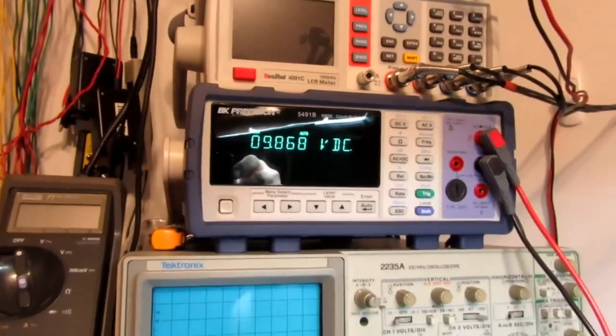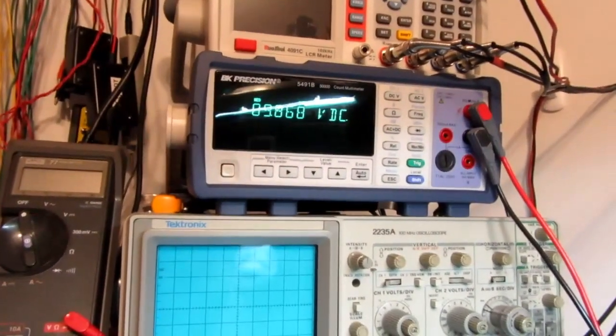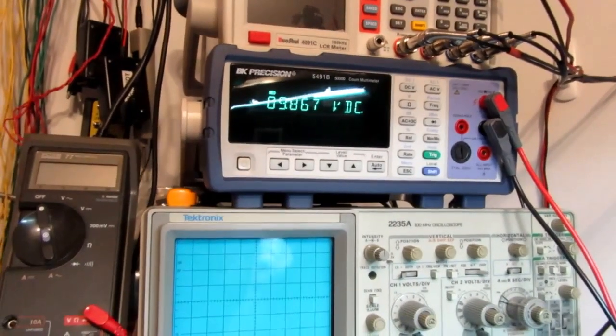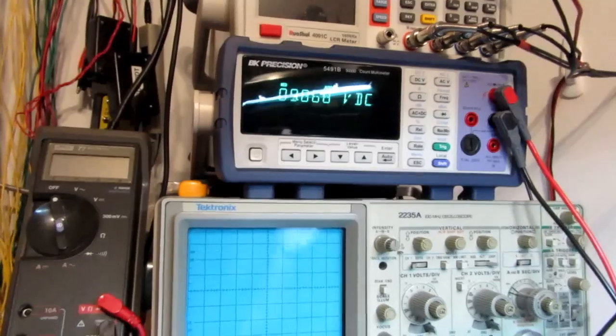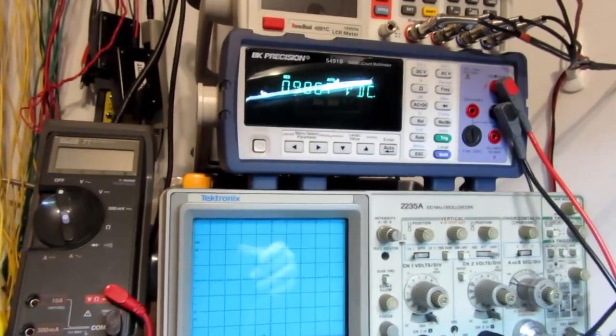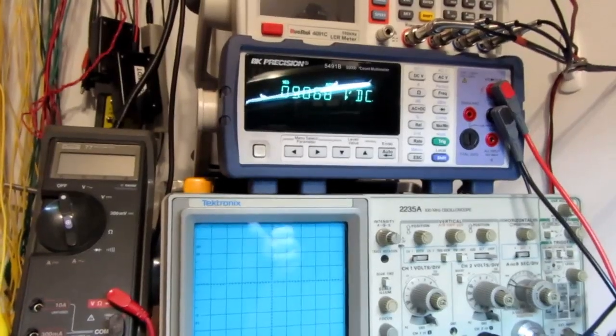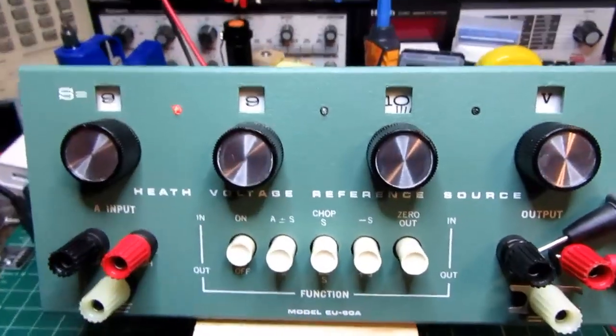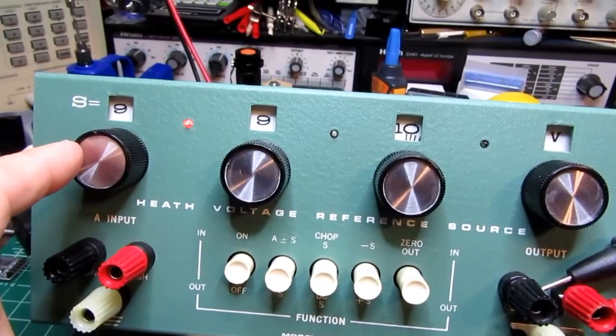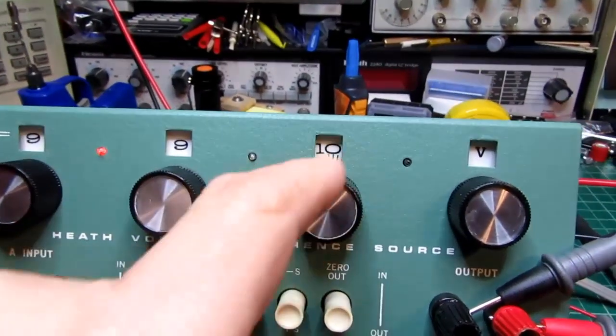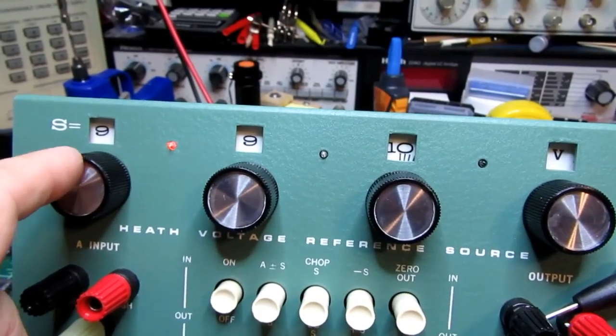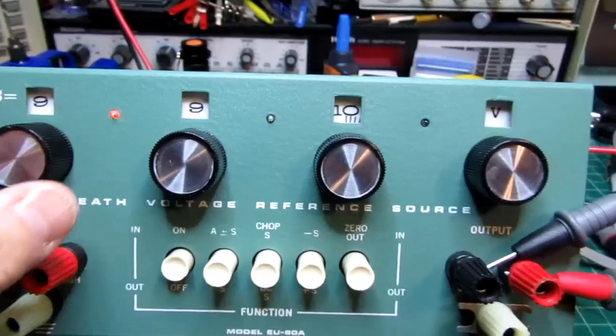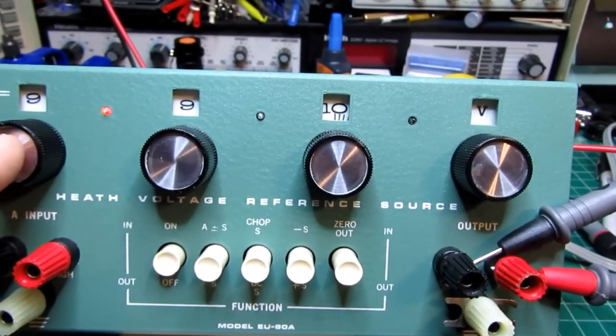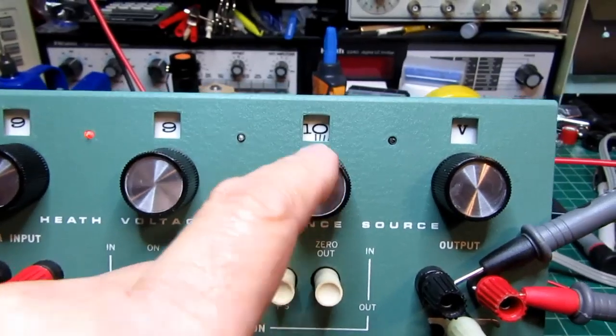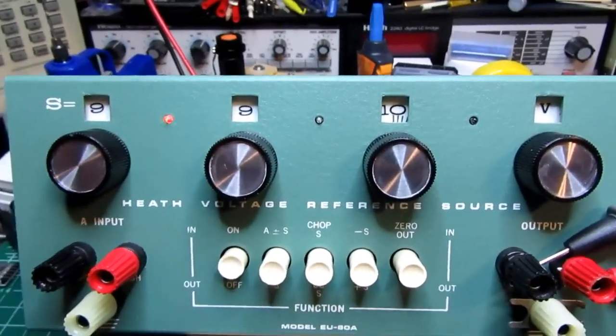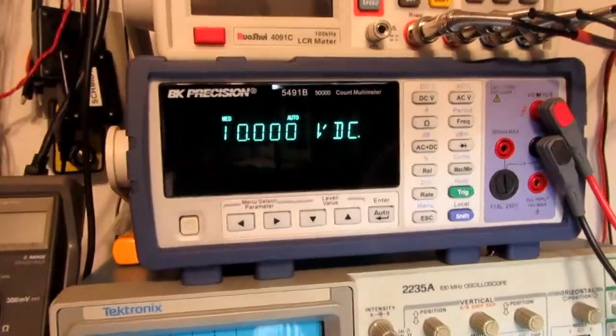I'm going to recalibrate it to read 10 volts exactly, assuming—like the other voltage reference—you're supposed to calibrate at the highest voltage output, since everything else is resistor-divided down, and you want to test without those resistor dividers involved. With this set to as close as I can get to 10—99, and it would roll to 9 but it rolled over to 1, so that rolls up to here—that should be 10 volts. And it is 10 volts exactly now.